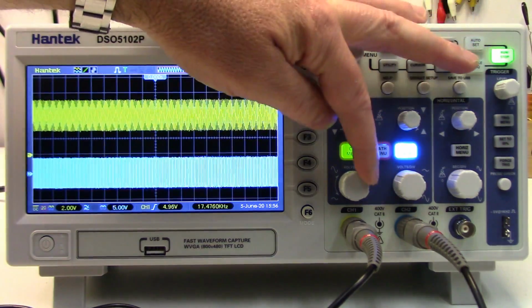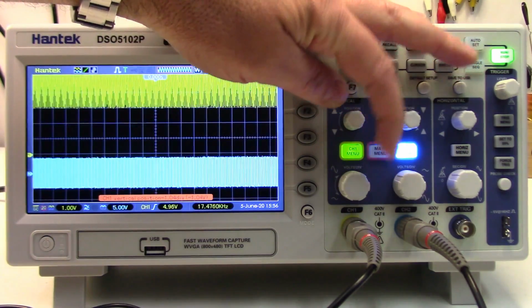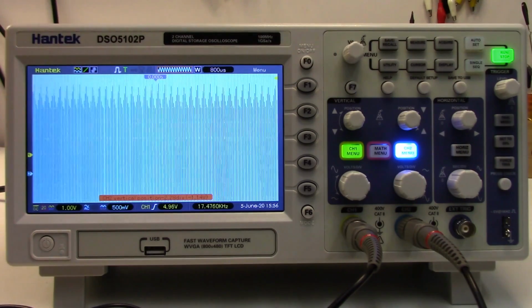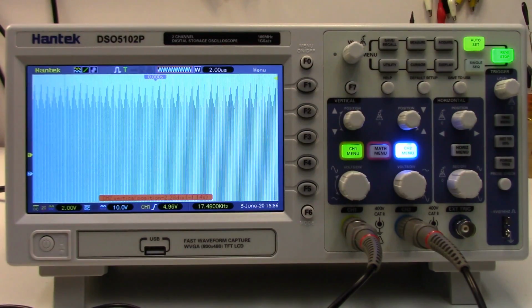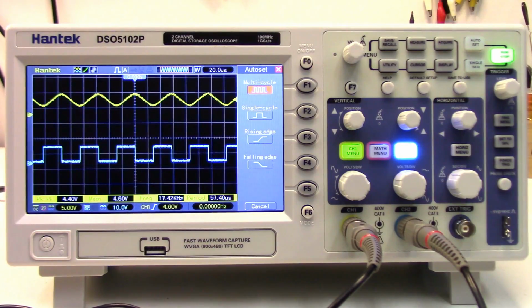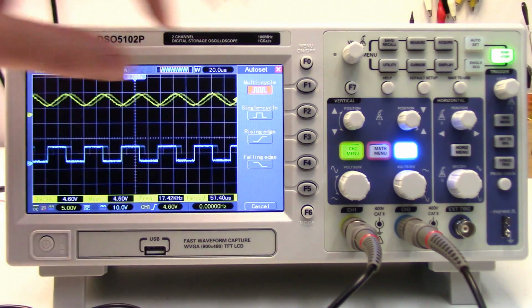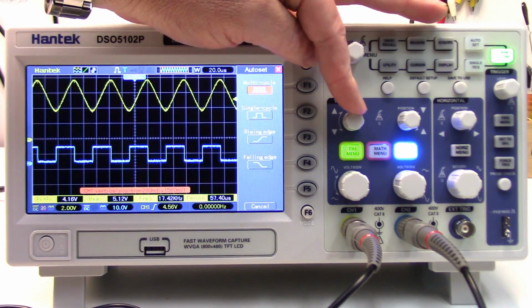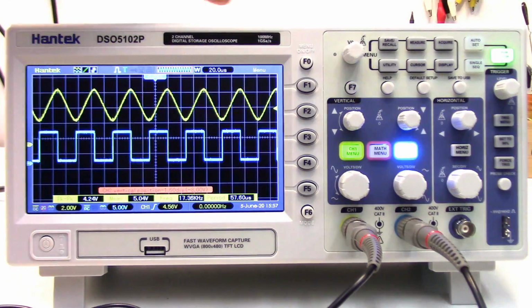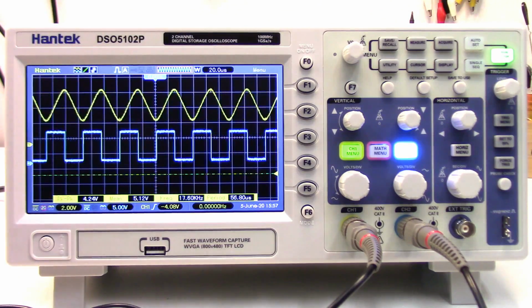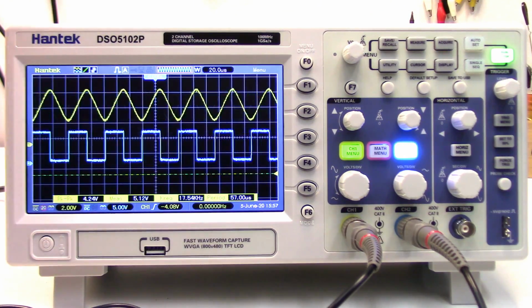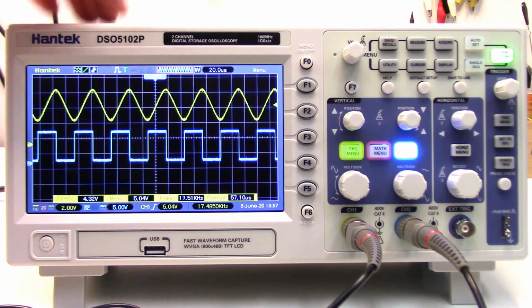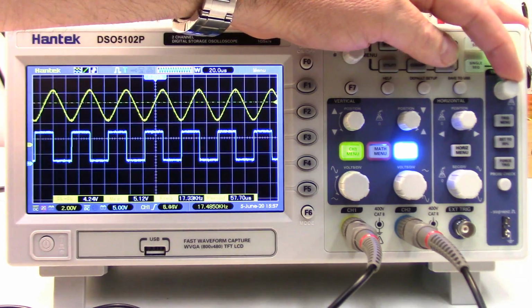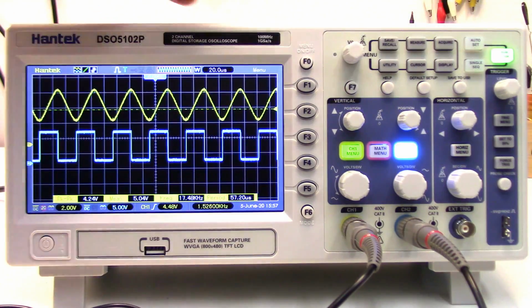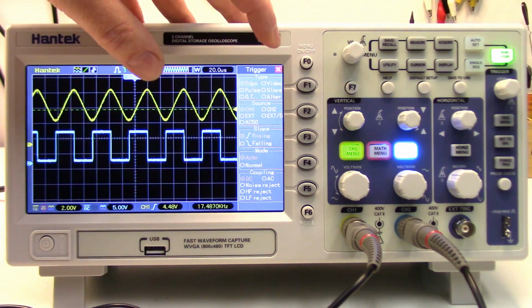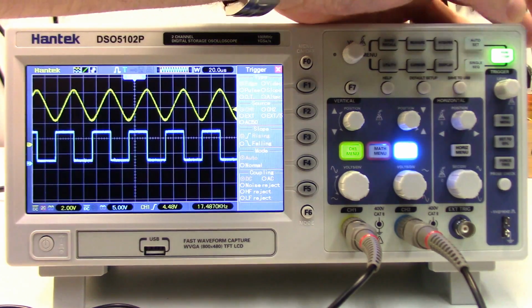But if you don't know what you're doing, if you've got something really screwy looking here, you turn it on, that's what you're getting. You can just hit this auto set, and this scope will select the best voltage and time scale to at least get you in the ballpark. And then of course you can move things around as you want. The other nice thing is the triggering. If things aren't triggered properly, the waveform will be dancing all over. You can just hit set to 50. It'll bring the triggering point to the center of your waveform, and of course you can also dial it up and down. And there's triggering menus. It'll show where it triggers. There's so much that this will do, but we won't get into all that.